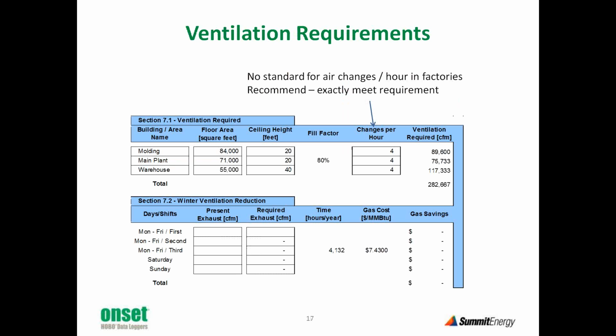Here's an example analysis. We often think of ventilation in terms of air changes per hour. If you have a facility and have no idea what the air changes should be or what the CFM should be, this is a simple calculation that will help you. In this particular case, I have 3 different areas of a building: a molding area, a main plant, and a warehouse. I know the area of the floor in square feet and the average ceiling height.